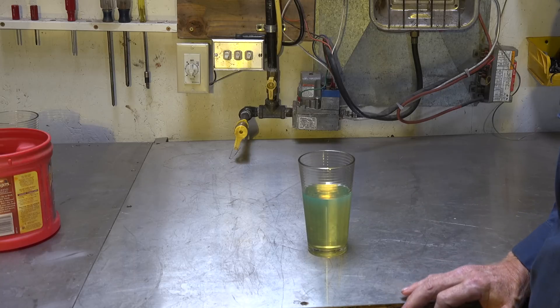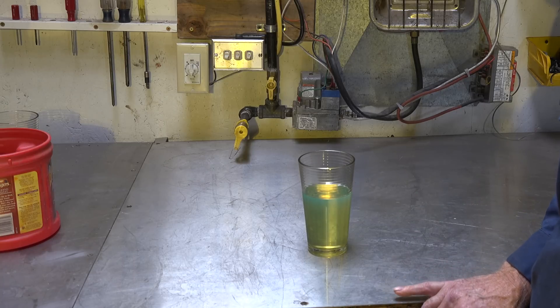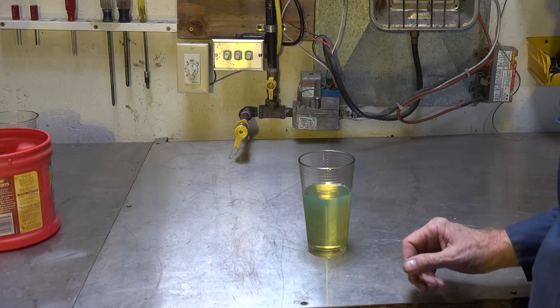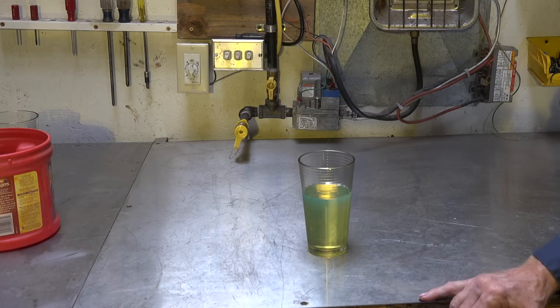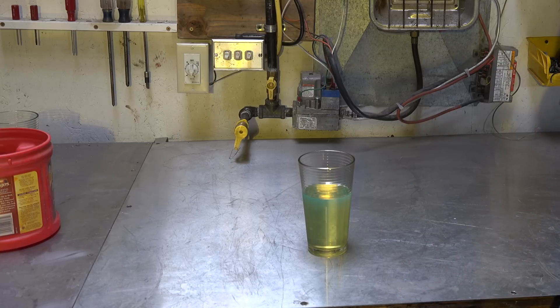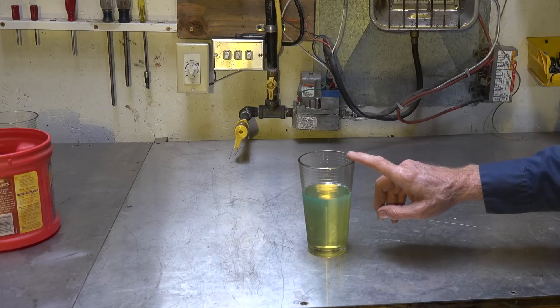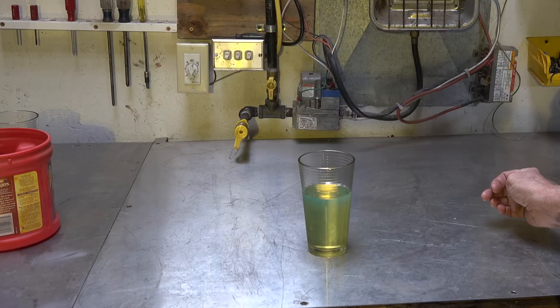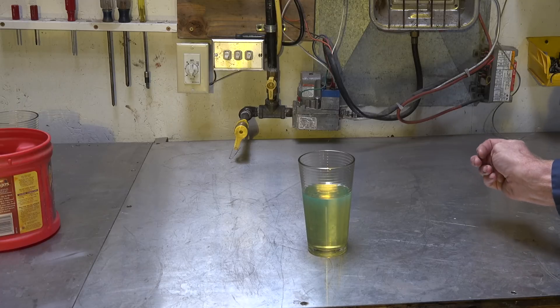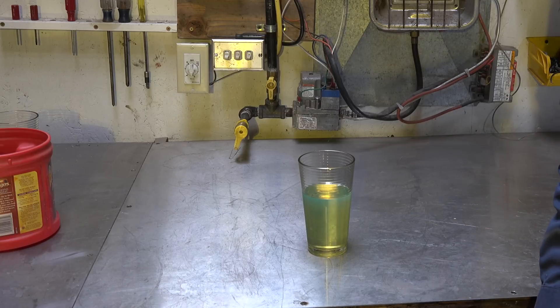Number one fuel oil runs 137,000 to 140,000 BTUs per gallon, compared to the 140,000 to 144,000 on number two. Number two fuel oil is also diesel — it's the same stuff. Now this particular sample came out of a diesel motor and would be used in tractors and things like that, but it can also be used in oil heating.